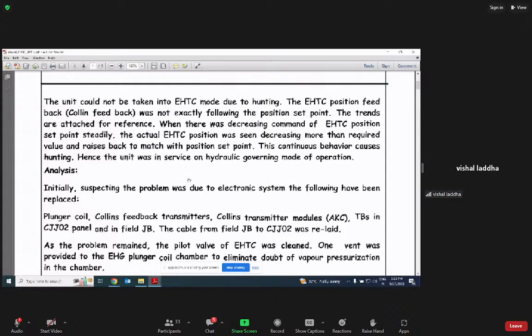So this is our line of action. Initially we suspected the problem was due to the electronic system. The following were replaced. In electronics, everybody knows that if this problem arises, the first doubt goes to the C&I department that the electronic system is malfunctioning. So C&I replaced the plunger coil, transmitters, transmitter module, the card, everything. The cable from field JB to CJJ02, which is nothing but the EHTC panel. They replaced all the electronic modules, but the problem remained the same.